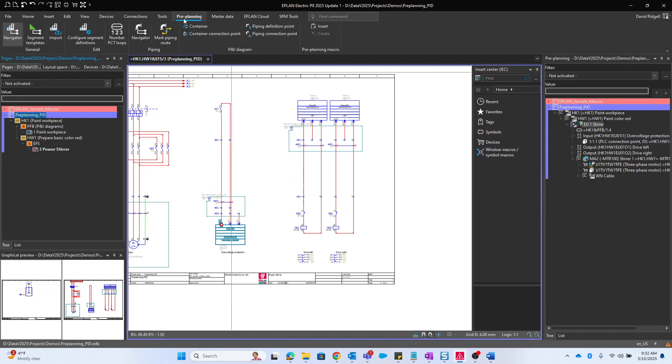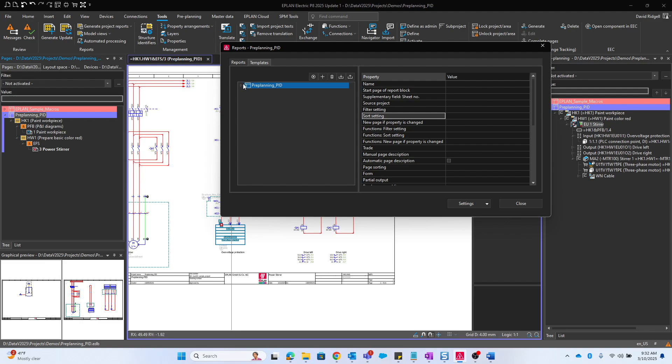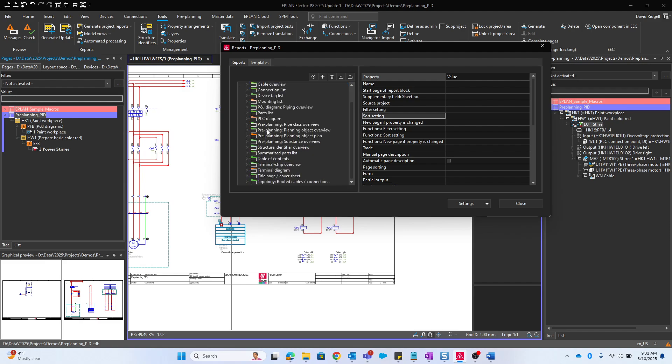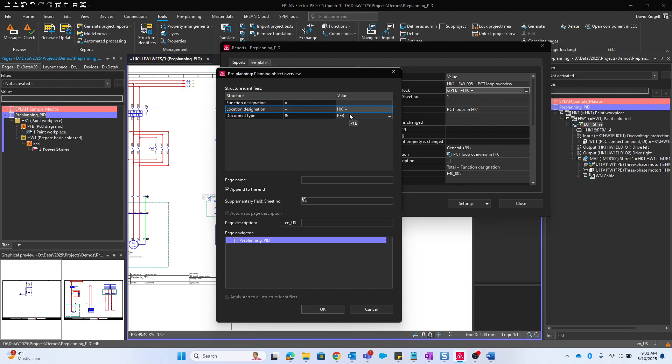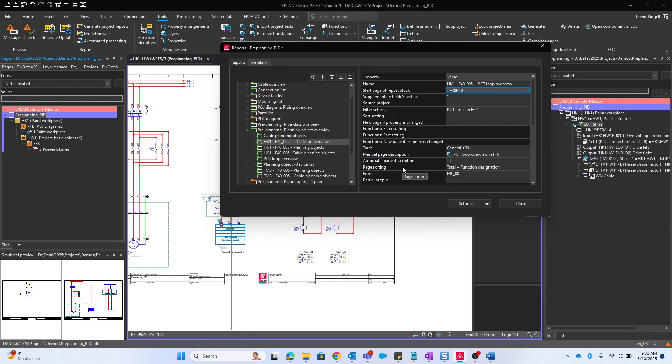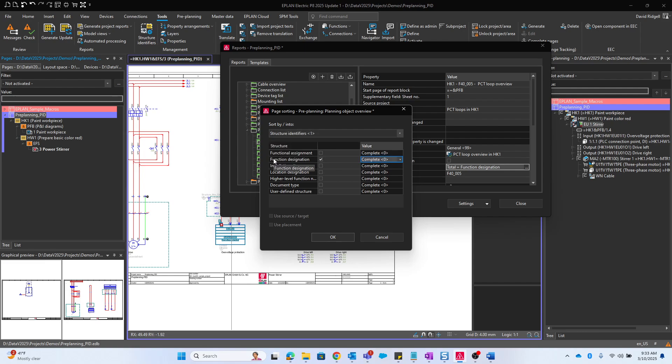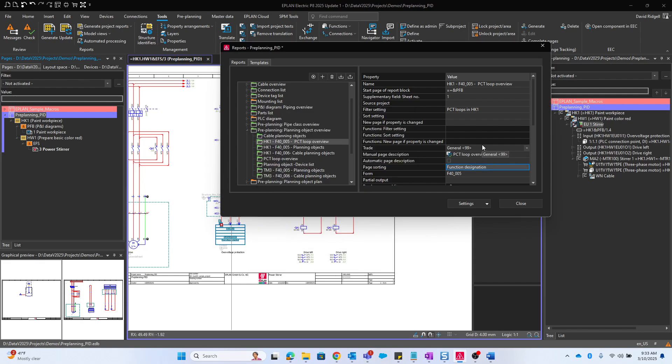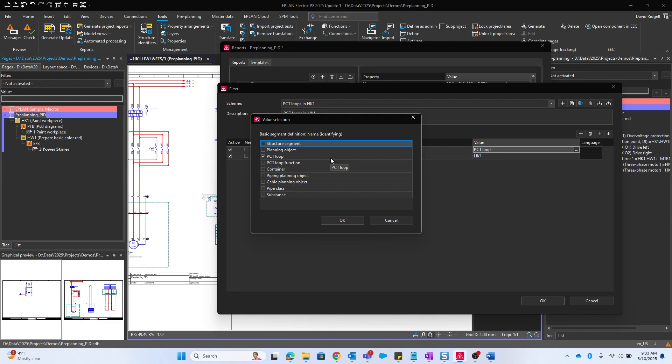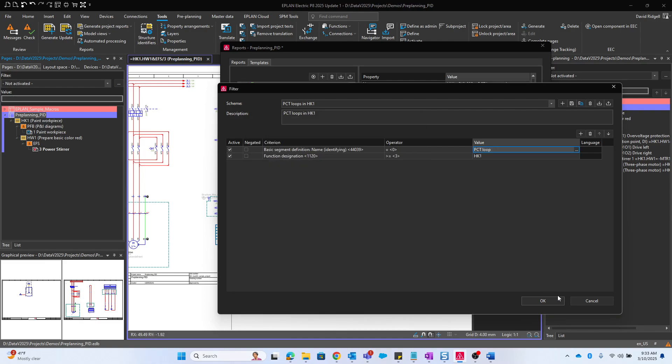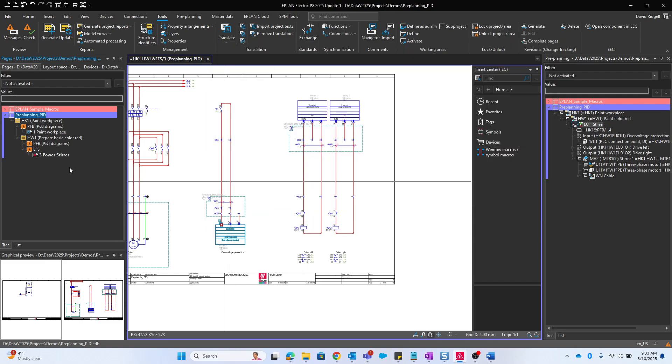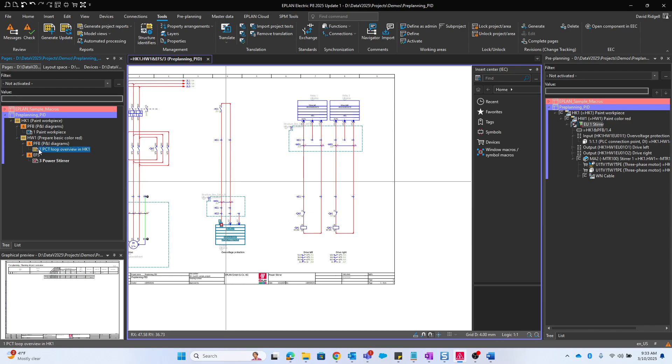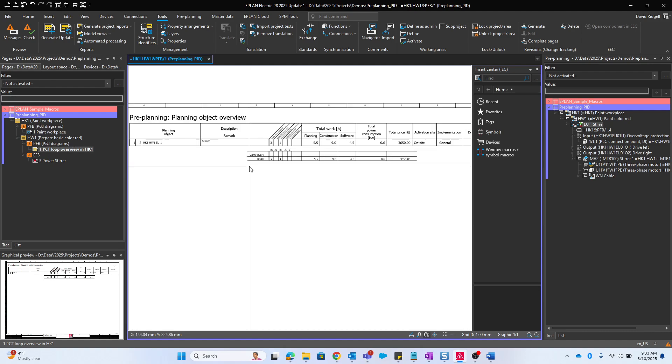We can also run some reports. There's several preplanning reports. For example, planning object overview. If we wanted to look at the PCT loop overview, that's this one here. I want to make sure that the start page of report block is set up correctly. We can just get rid of the location, make sure the page sorting, I'll change that to just structure identifiers and sort it by function designation. We'll look at the filter setting. We're going to get all the PCT loops. Let's go ahead and generate that. Here we have our PCT loop overview showing us all the properties of our loop.